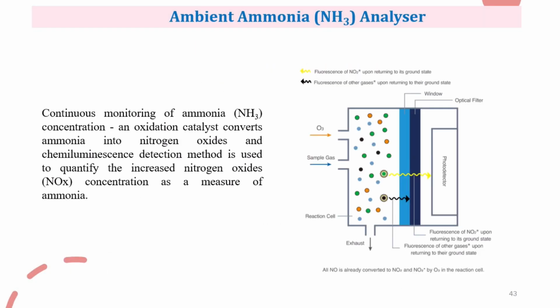Continuous monitoring of ammonia concentration: an oxidation catalyst converts ammonia into nitrogen oxides, and a detection method is used to quantify the increased nitrogen oxides concentration as a measure of ammonia.